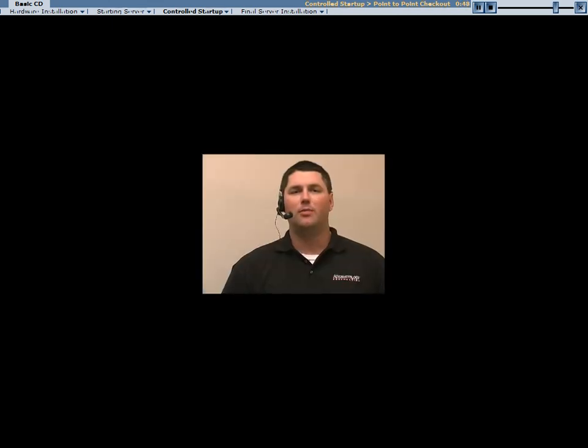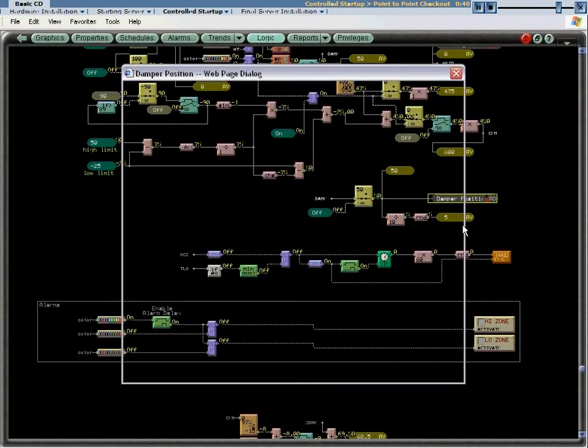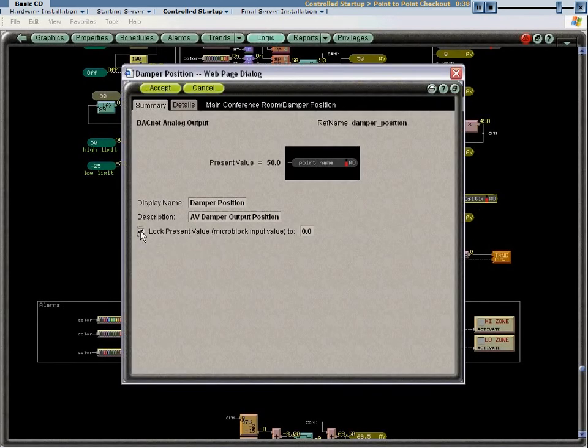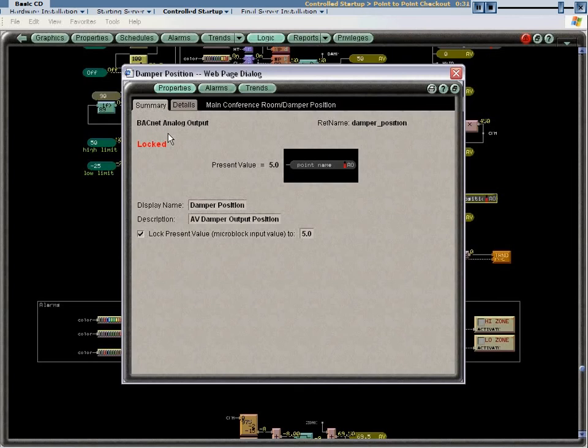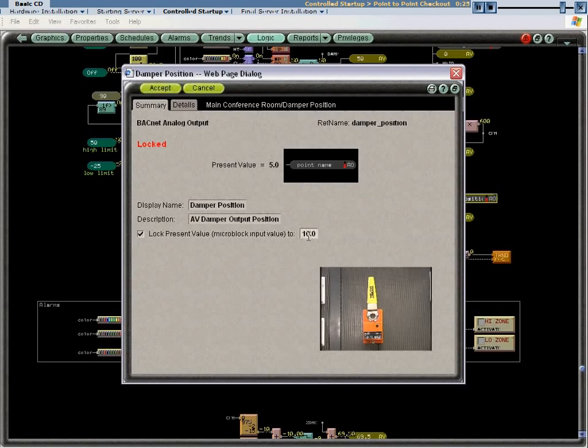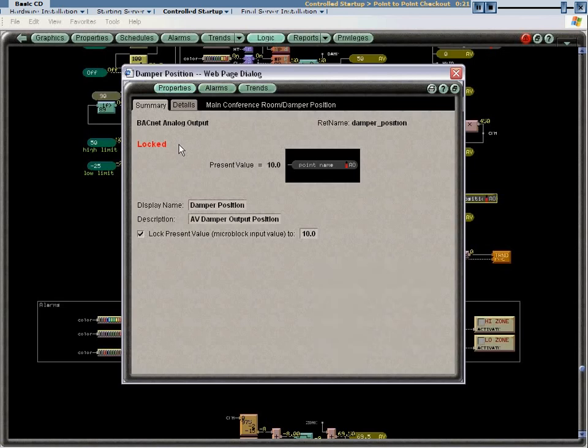For the analog outputs, verify the output or actuator type and the min-max values are configured correctly. Next, lock the AO to the desired output, such as 5 volts. Then verify the movement of the end device to the desired position. Next, lock the voltage output to the device maximum, such as 10 volts, and verify. Finally, unlock the point.